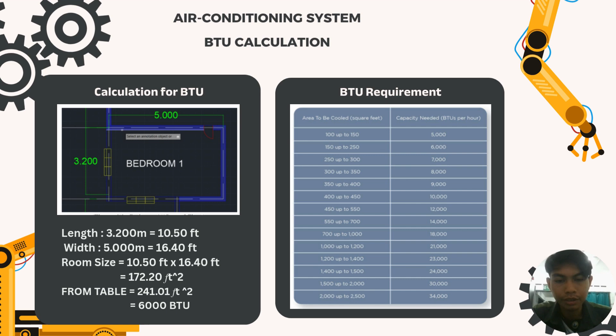The area is, the length is 3.2 meters equal to 10.5 feet. Width is 5 meters, equal to 16.40 feet, and the room size is 172.2 feet squared. From the table, we can see how much BTU value is needed for this space. So this is an example to calculate the BTU value. You can see in the slide the example, and after you get the value, you can refer to this table so you know how much horsepower your air conditioner should have.